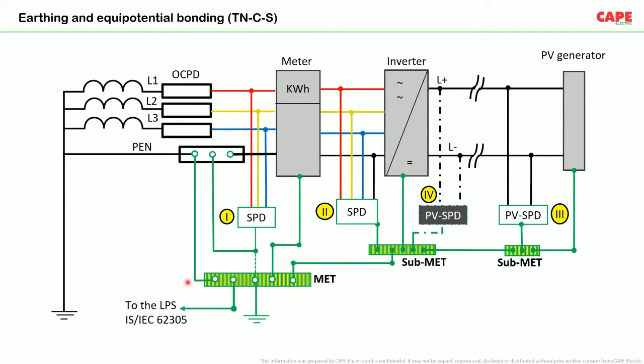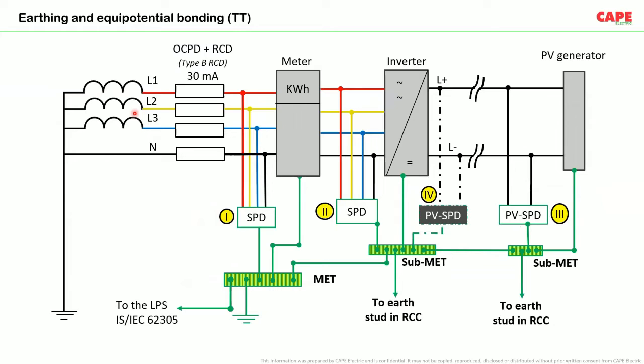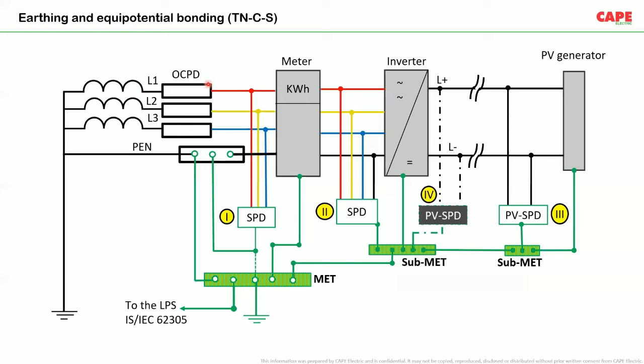The difference between TT and TNCS: in a TNCS network, the incoming PEN is connected to the earth bus bar of the installation. So there is a metallic fault return path to the source, to the neutral of the transformer. Whereas in TT, there is no metallic fault return path. As a result, please look very carefully at these protective devices where I am pointing the cursor: OCPD plus RCD, type B RCD, 30 milliampere. In the previous case, in a TNCS system, of course, OCPD is enough for basic safety.